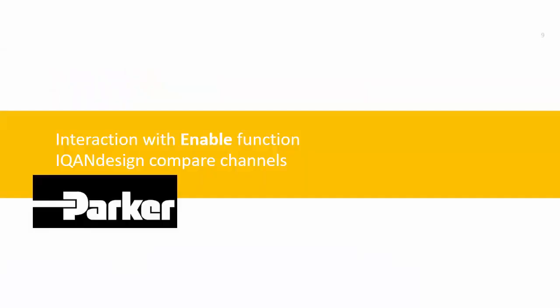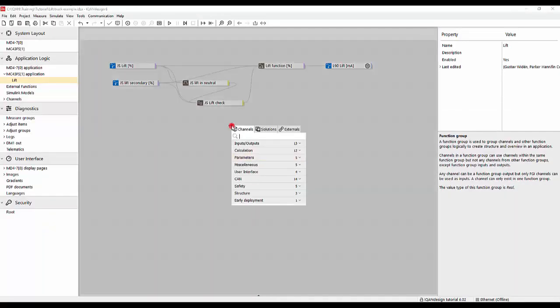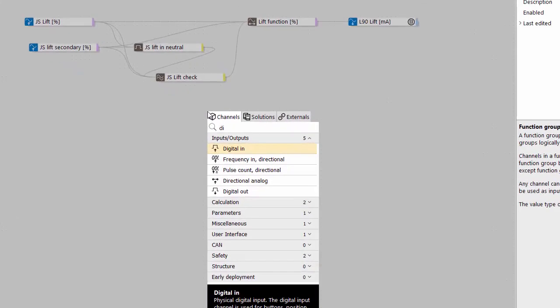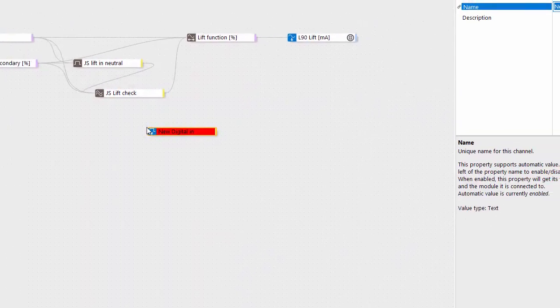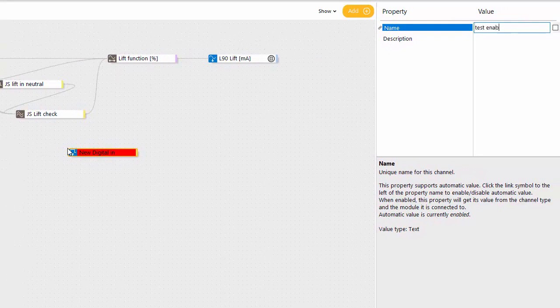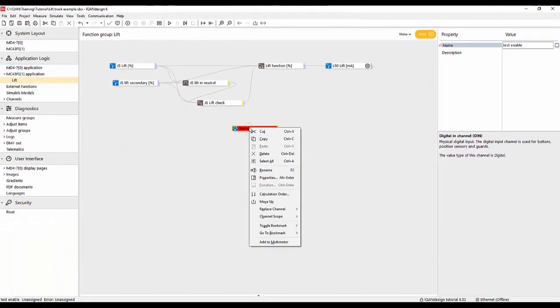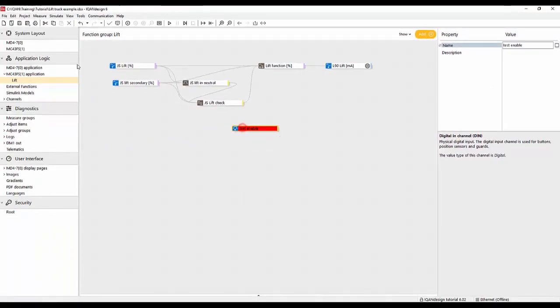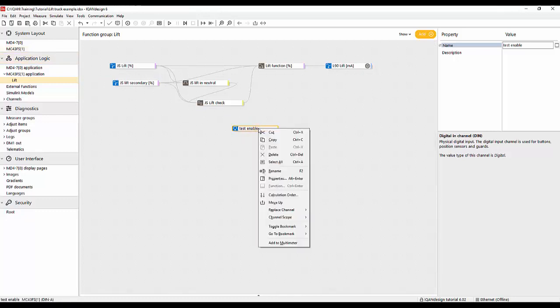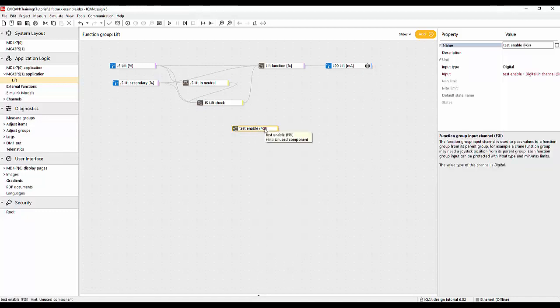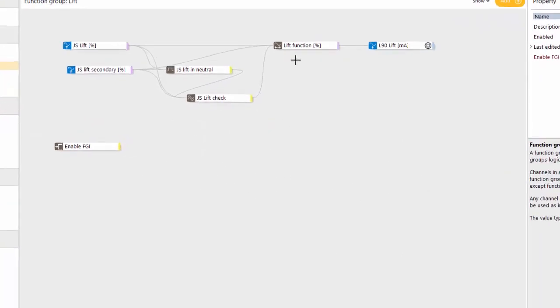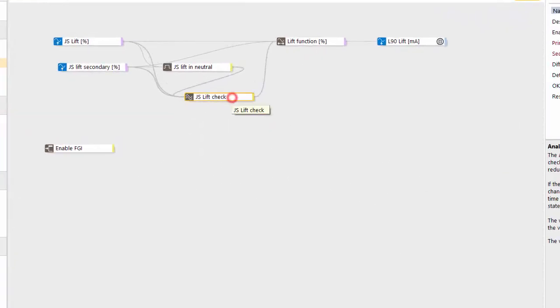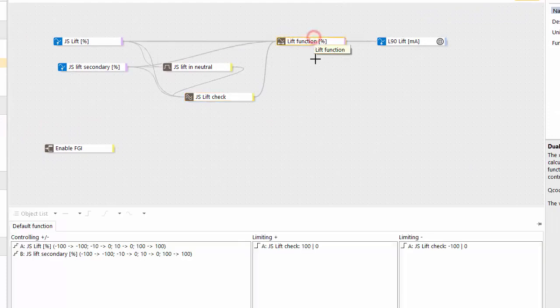So we want to combine this lift function now with some other enabling functions. So to do that let's just add one digital input that will just use as a test input like test enable. So this will come from some other safety function and we put that on the MC43. It should come from somewhere else so let's turn this into, or insert in between, a function group input using that move up function that I showed and call this enable FGI.